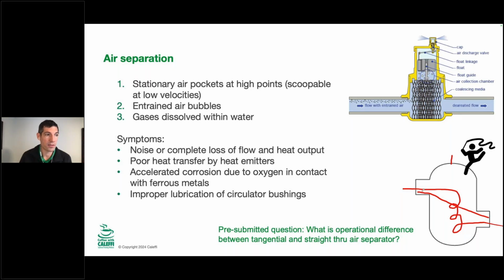So if you see a tangential air separator, it's going to have a very specific flow rate that it likes. It has to be enough to create that vortex to be able to have the air swirl around in this device and come out the top. If it's too low or if it's too high, you don't quite get that same performance out of those devices.